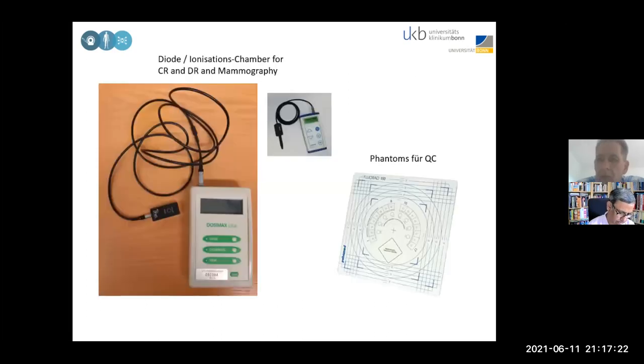I'm not paid by the vendors, so that's something I have to say in advance. This is just a little overview about machines you could actually use. These are not my machines, only the one in the lower left corner is mine, and the other ones are used by other colleagues. These are those meters for mammography on the left side, and the one in the middle is used for X-ray machines. And for the QC, you see on the right-hand side, for example, one of those quality phantoms.